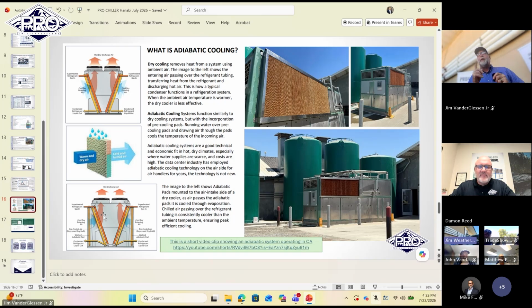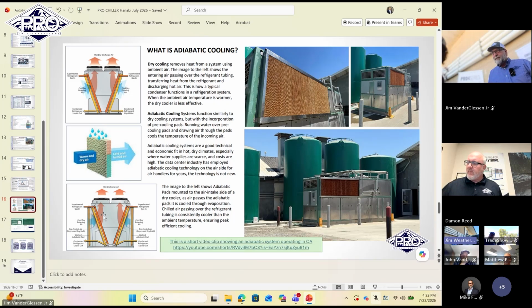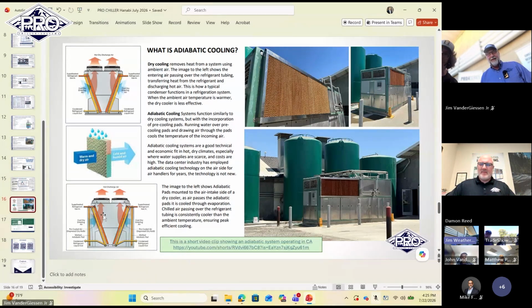What we've installed on this system here is a sensor measuring the air outside the adiabatic pad, and then a sensor measuring the air inside. Nick, you were watching it yesterday. You saw some interesting results. Yeah, it was operating yesterday, and the ambient air was about 95 Fahrenheit. And then the temperature on the backside of those pads was 69, which seems nice and mellow as far as the chiller is concerned. So that was nice to see.